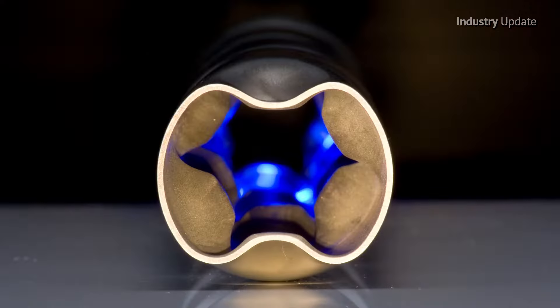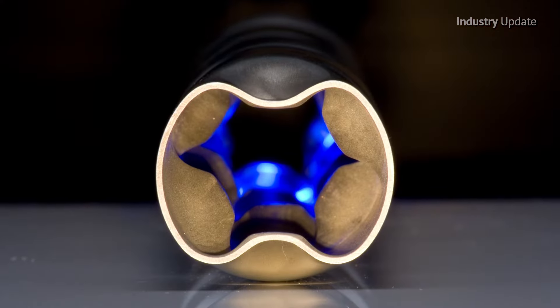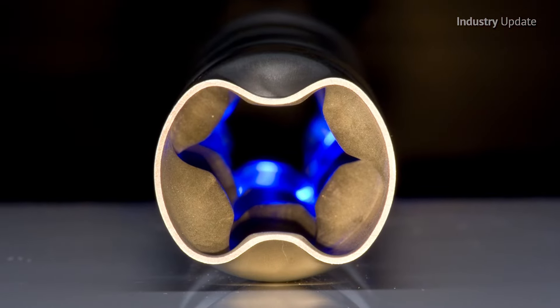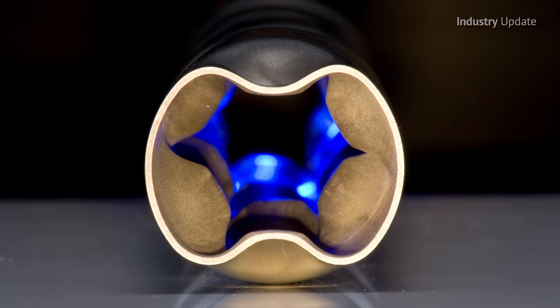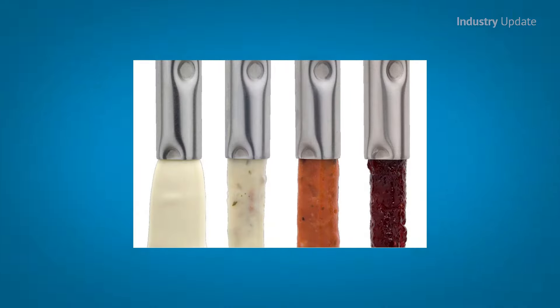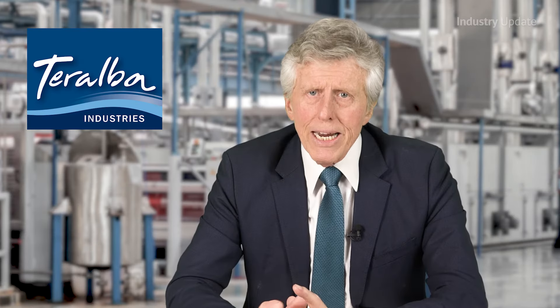The Dimple Profile is used to increase turbulence in the product and service media. This turbulence results in a high heat transfer coefficient, even when processing viscous products such as slurries and sludge. A clear drainage passage in both the product and service channels provides the ultimate in hygiene, achieved by the unique arrangement of the Dimple Profiles.